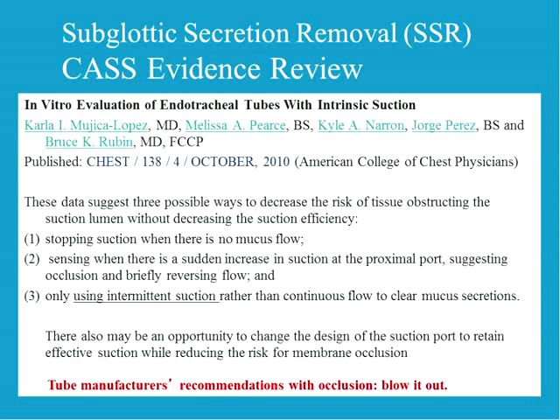Now, one thing I want to raise here is the tubing manufacturers recommend that when you suspect that port is occluded, you should blow that out. In other words, you should take a syringe and put positive pressure back through the tube, not negative pressure. There's a couple of vacuum regulator manufacturers out there that have what seems like a good idea at the time, I'm sure, but it's a push to clear type of button, where if you sense that tubing is occluded, you hit the button and it exposes that port to full wall vacuum. So that is contraindicated. I would never use such a feature. If you suspect that it's occluded, you should blow it out with a syringe per manufacturer's recommendations.